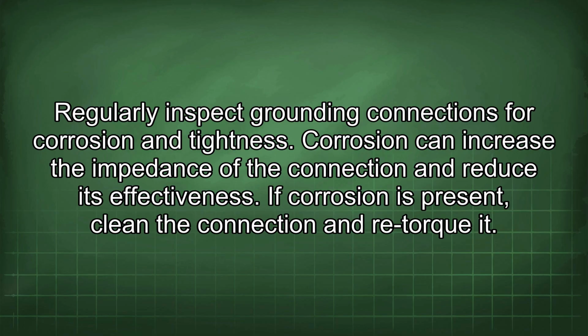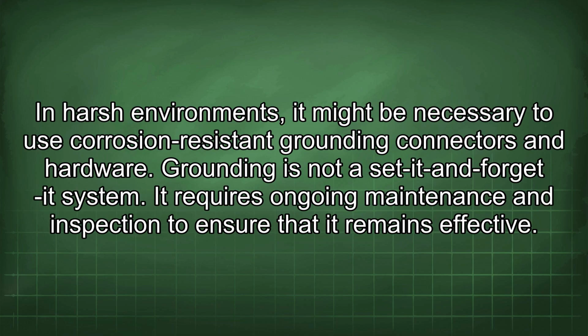Corrosion can increase the impedance of the connection and reduce its effectiveness. If corrosion is present, clean the connection and retorque it. In harsh environments, it might be necessary to use corrosion-resistant grounding connectors and hardware. Grounding is not a set-it-and-forget-it system. It requires ongoing maintenance and inspection to ensure that it remains effective.